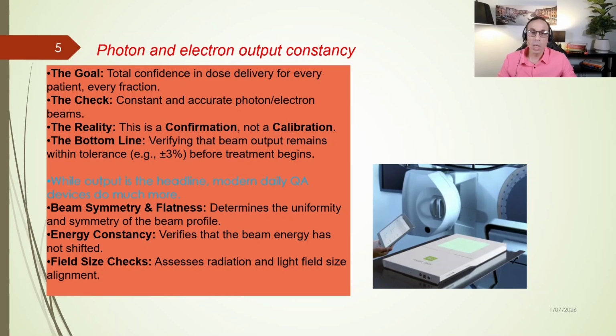We are not here to fine-tune the machine output. We are here to verify that the machine is still performing exactly as it was calibrated by the physics team. The bottom line is patient safety. We are ensuring that the beam output remains within a tight tolerance, typically plus or minus 3%.